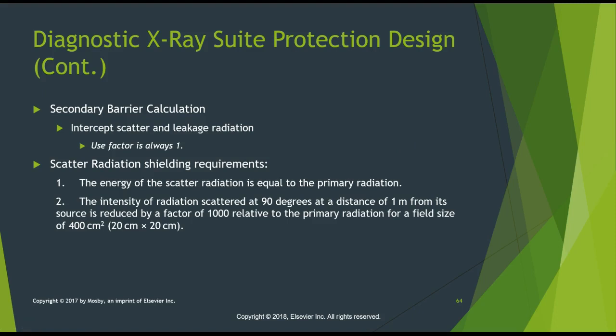Scatter radiation shielding requirements. The energy of the scatter radiation is equal to the primary radiation. Okay, the intensity of radiation scattered at 90 degrees at a distance of 1 meter from the source is reduced by a factor of 1,000. You need to remember that. That's an important number to remember. Just remember it's 1,000.